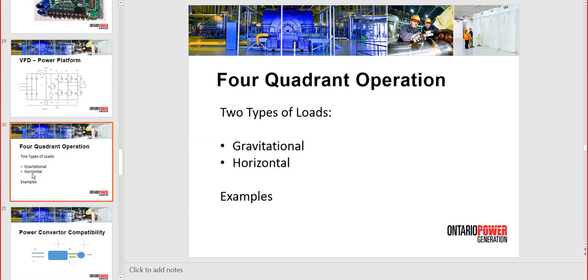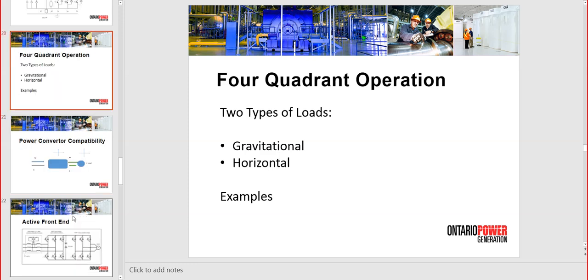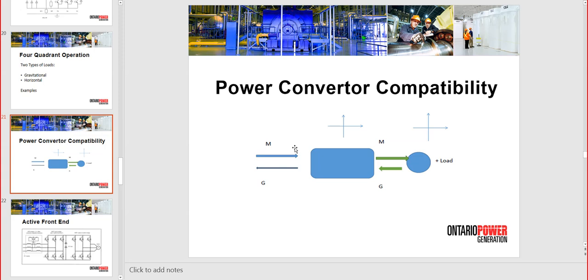Okay, and here is the 4-quadrant operation. There are 2 types, gravitational and horizontal, and this is how we need to think about this. You actually have a 4-quadrant load, because the load is 4-quadrant. It can go forward, reverse, it can go up or down in case of a crane, and then the actual current and voltage need to change on the VFD to accommodate that change in the motor with the load. So the motor with the gearbox and the load behaves in a certain way, and we need to accommodate that with the VFD. So very important.